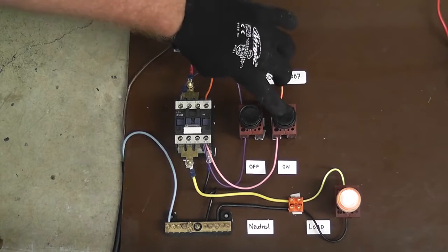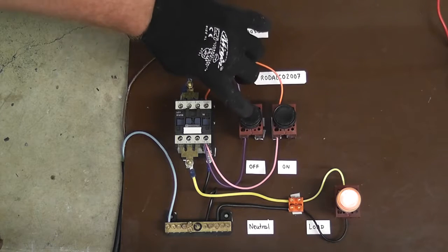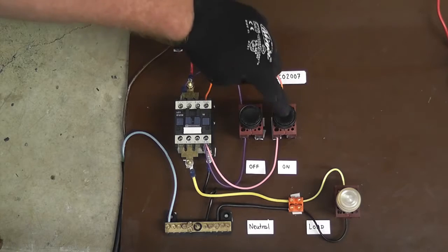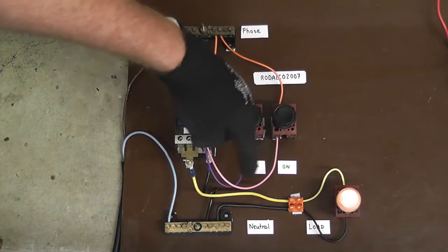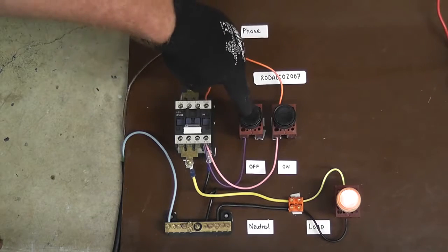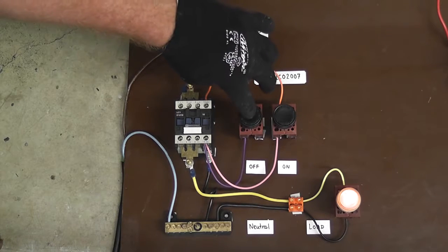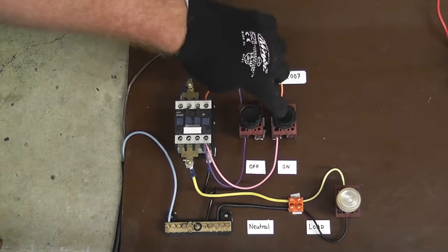The actual on button is a normally open contact, the off button is a normally closed contact so power goes in, I make contact, the relay gets energized through here, that contact is closed, drives the relay coil, pulls the relay in, stays on. Touch this button, off, relay falls out, load lamp is off.